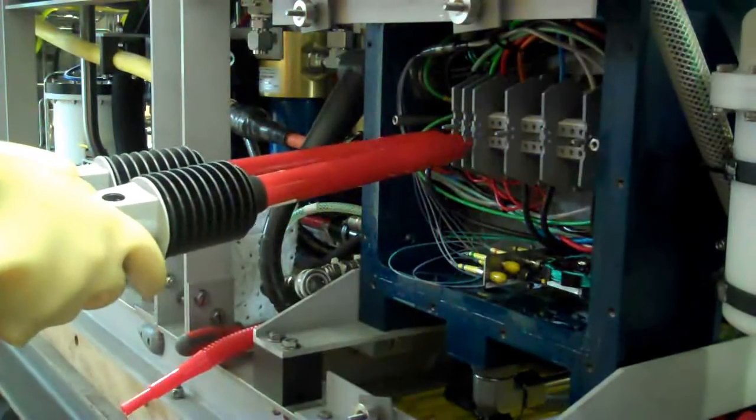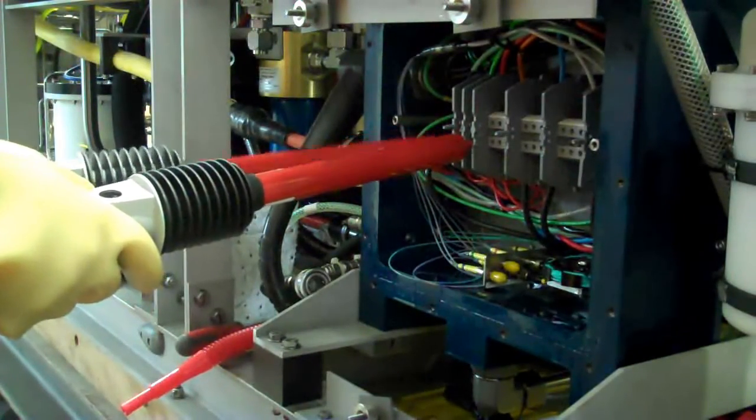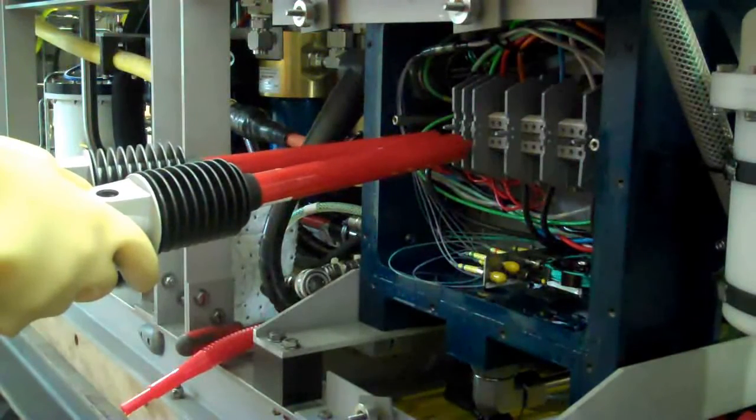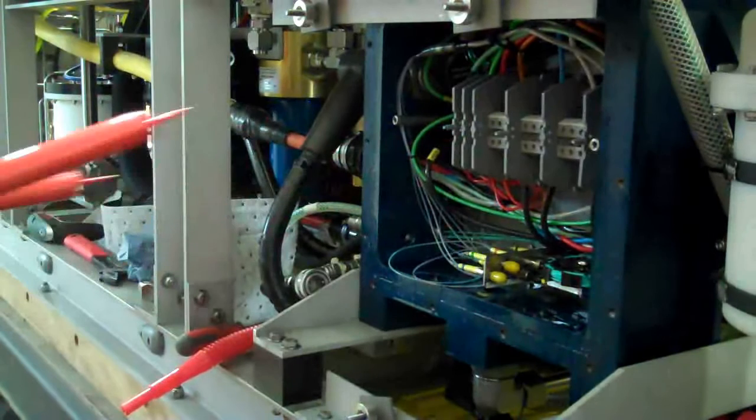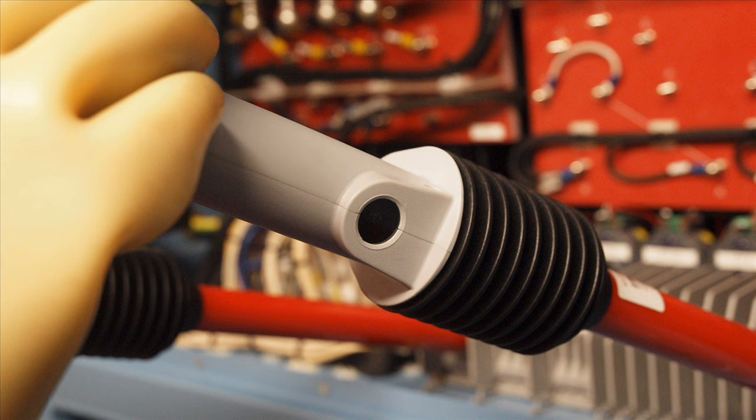The engineer now tests between phases on the main power conductors. He also tests between phase and earth. If the light on the probe were to glow it would indicate that there was a voltage present and the system would be unsafe to work on and the source of the charge must be investigated.